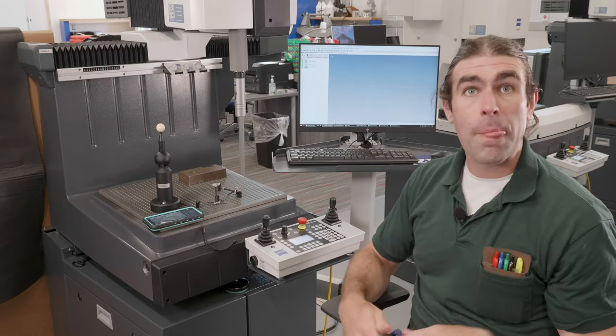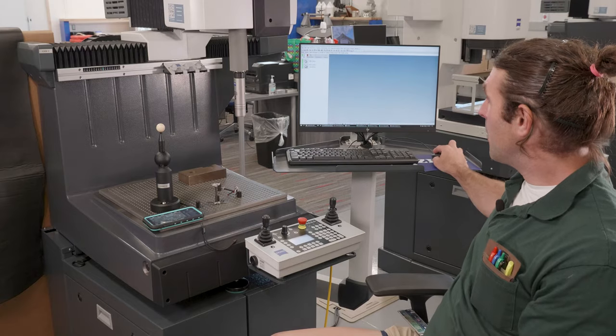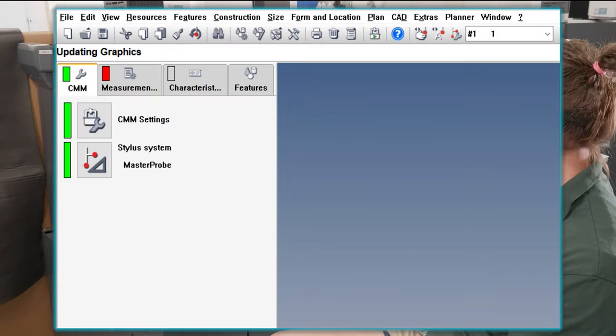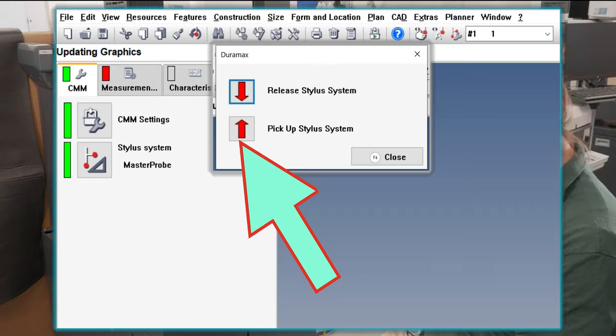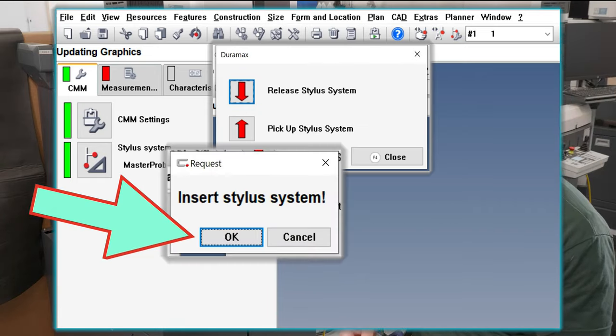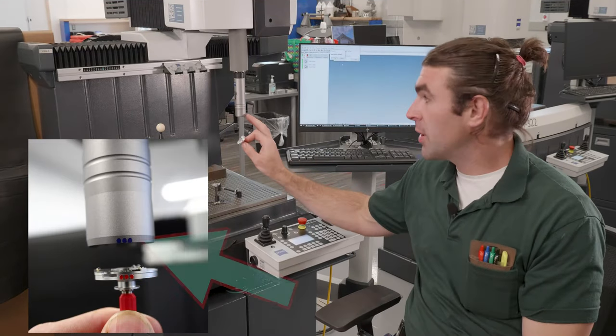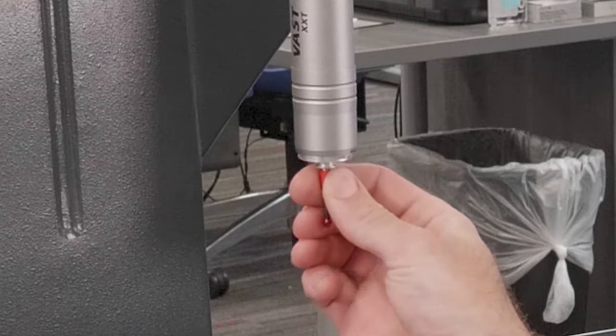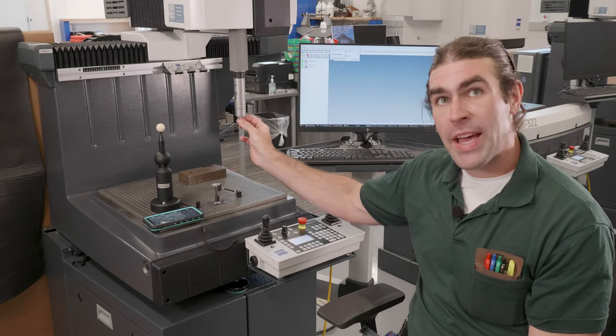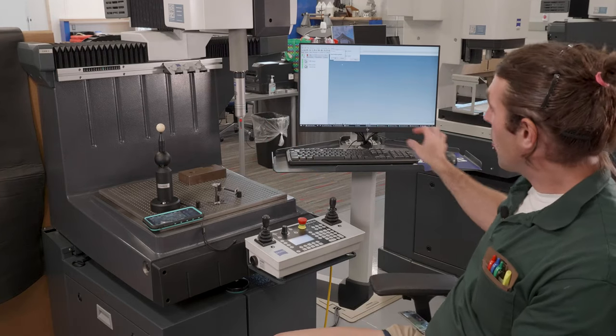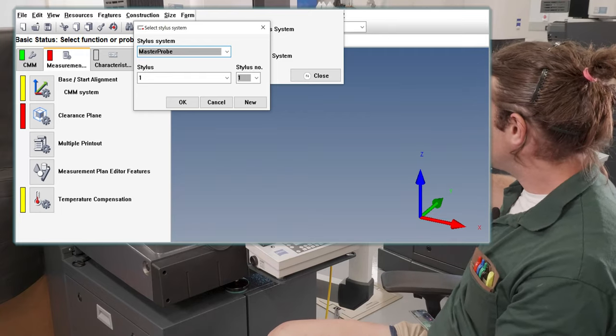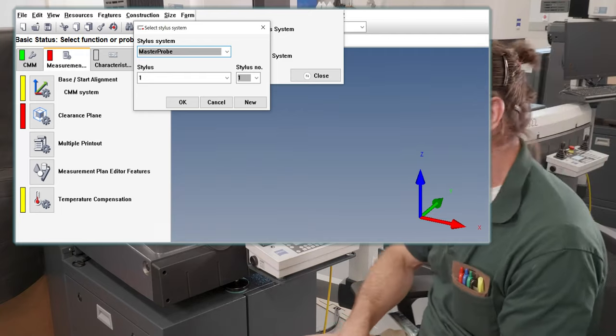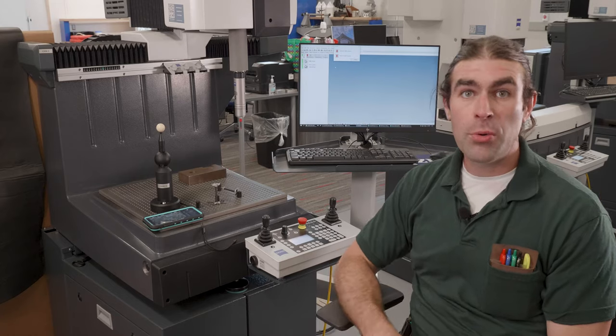So to load the master probe, I got to tell the machine what we're doing. So I'll go to the screen here. It's in the middle top of the title bar. Manual stylus system change. I want to pick up a stylus. So this button right here tells me to insert the stylus system. And I'm going to do just that. All I want to do is line up. There's three little red dots on here. There's going to be three little blue dots on here. I'll line them up and there's a little magnet that grabs it. You can kind of twist it back and forth and make sure it's locked in there. I'm going to hit okay on that dialog. And then I'll select the stylus system. I'll select master probe and hit okay.